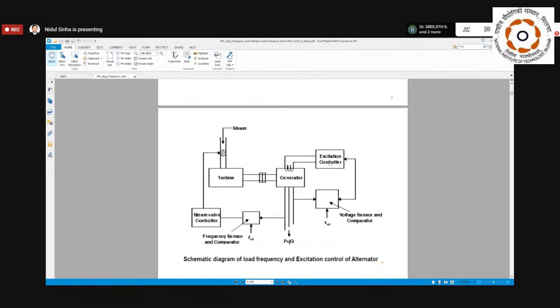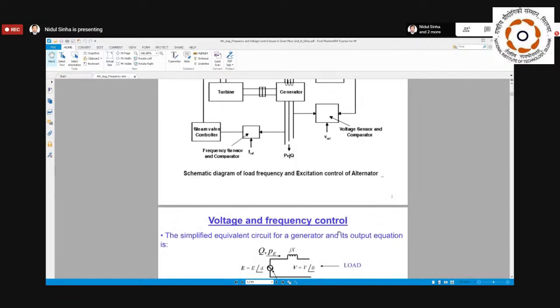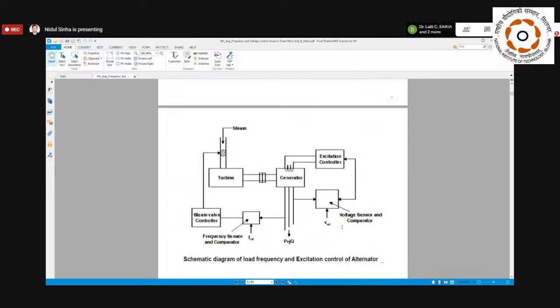We find that the voltage is dependent on the excitation. I'm not going into the fundamental concepts of excitation, but with varying excitation we can vary the voltage induced in the generator.